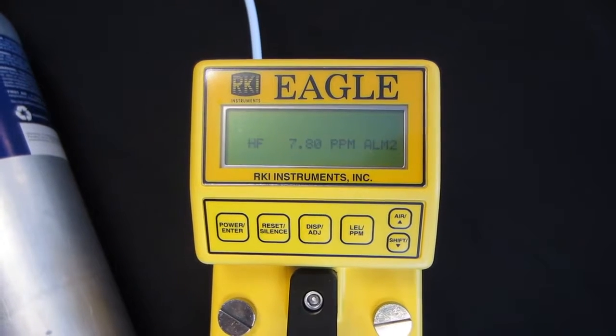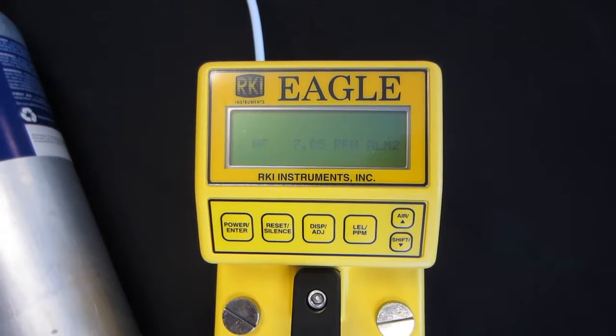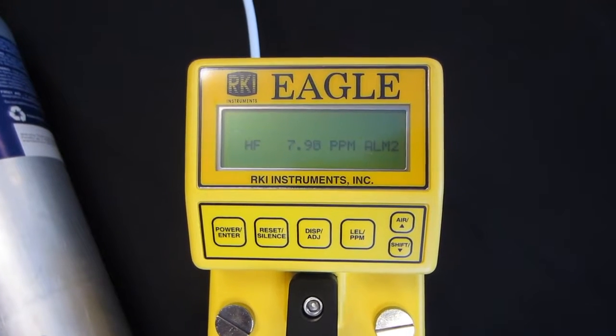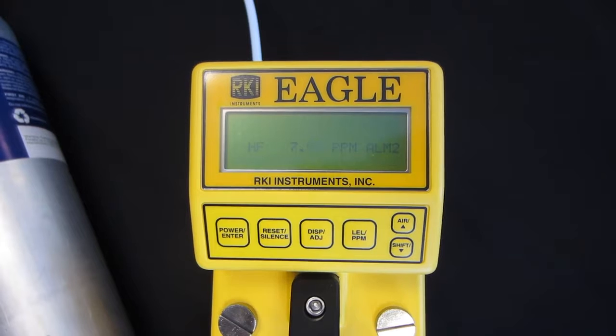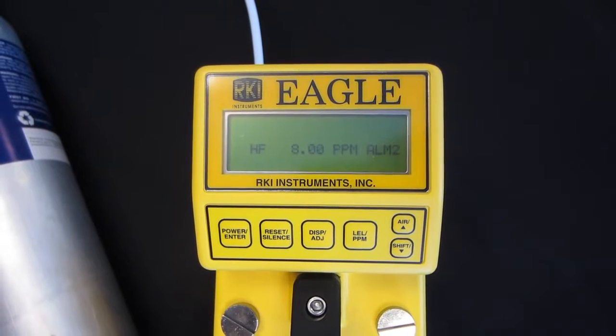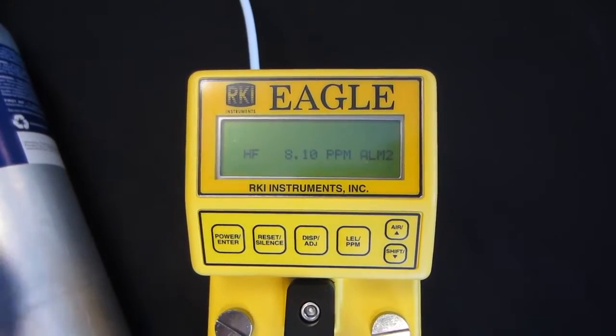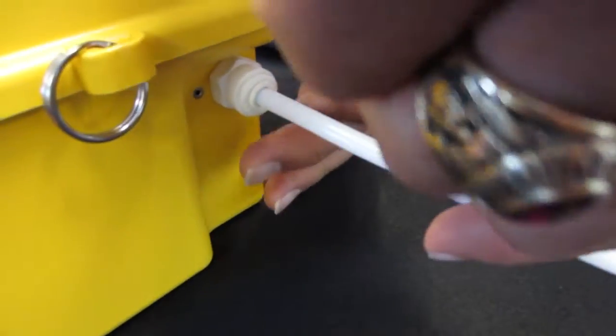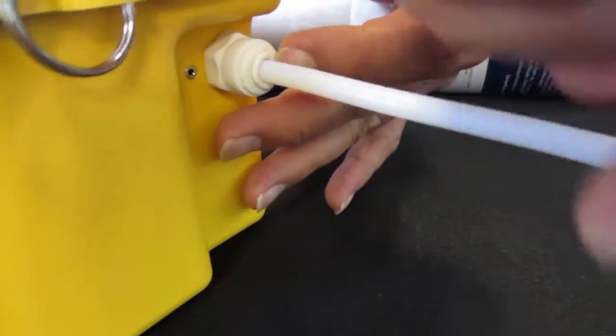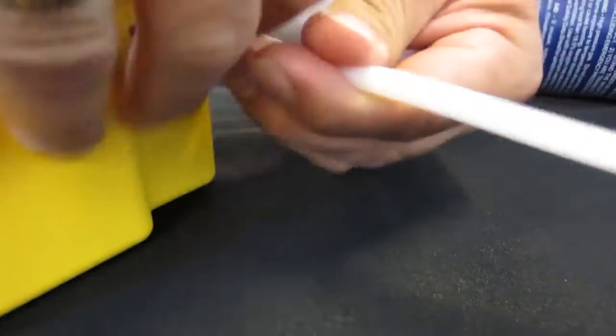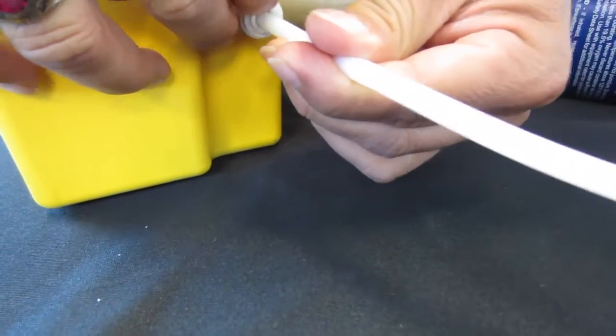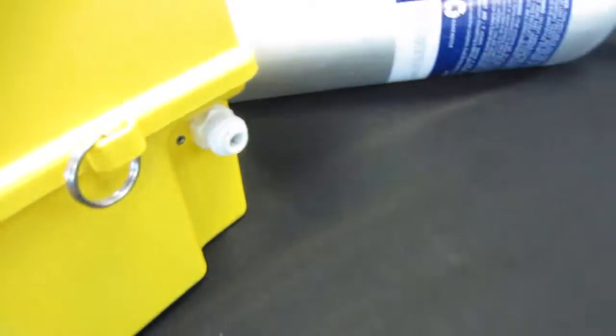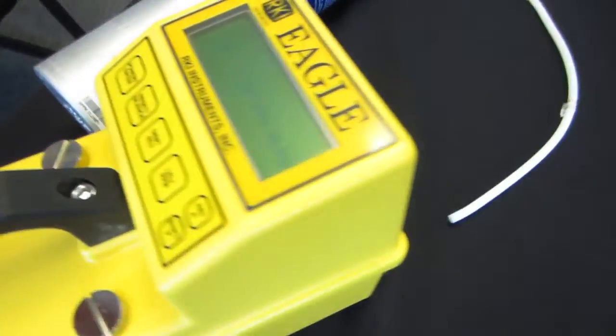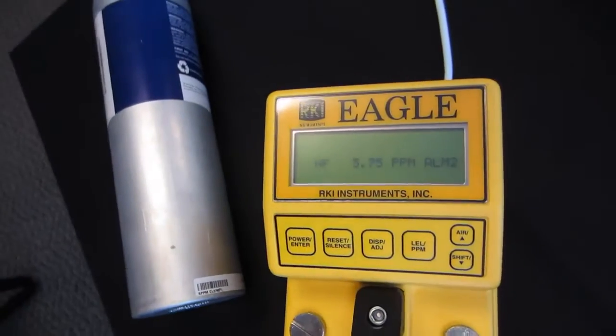And there's different things you can do to validate a bump test. That is, see how far it goes, how close. We're at 8 ppm now, so we're not even at a minute and a half yet. So I'm going to go ahead and pull the gas off. And again, we want to push in the collar. Oops, I'm sorry. Okay, and then simply pull the tubing out. Okay, so the regulator shut off because I disconnected the tubing.